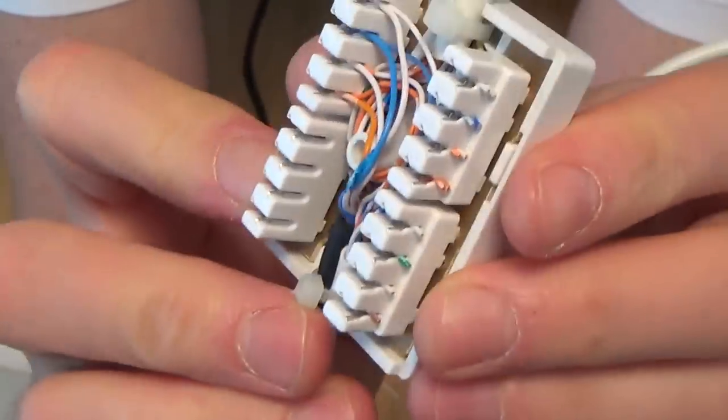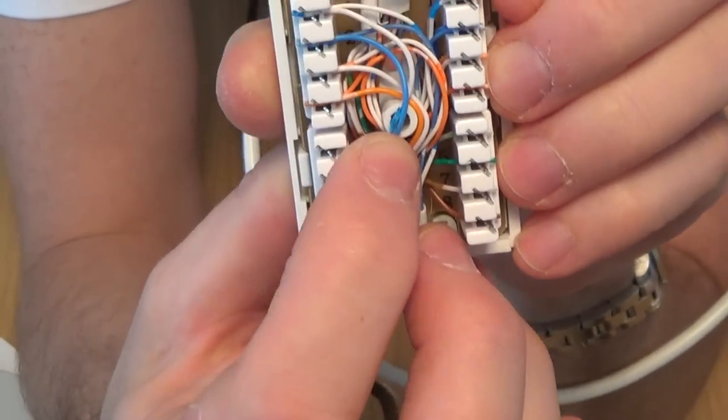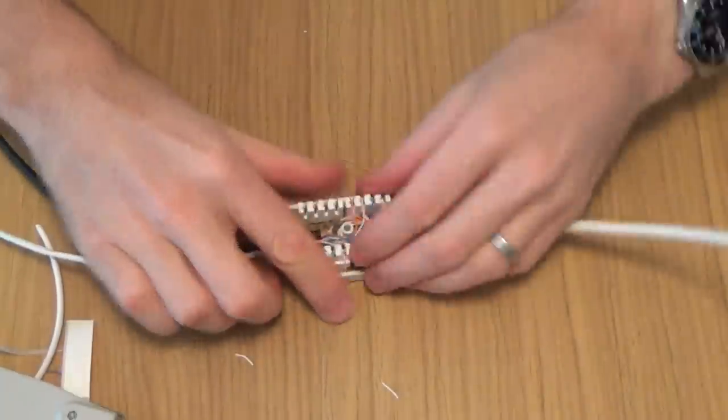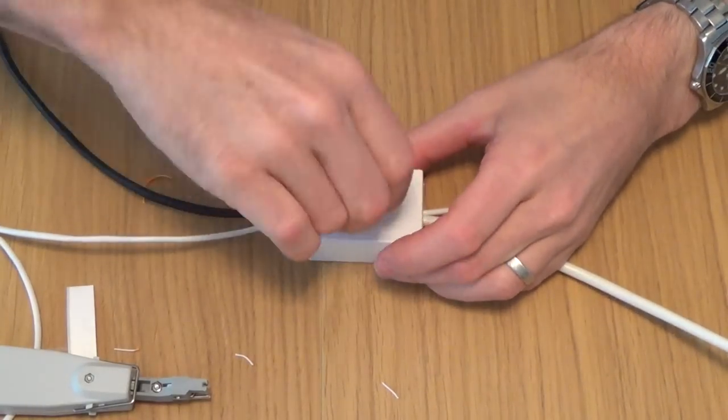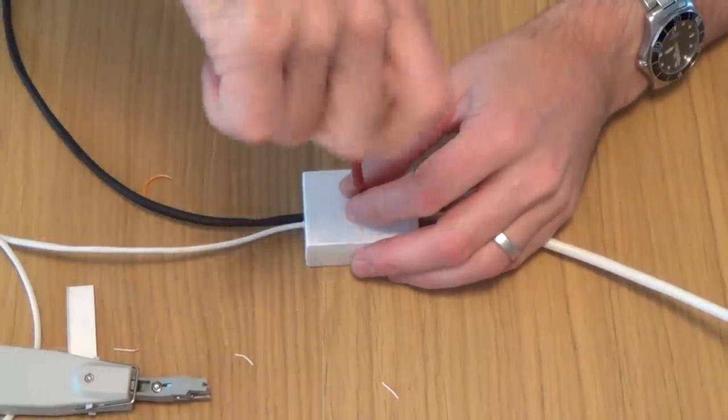You can see that when we put the lid on, that these wires are away from this hole here, because if you had the wires going over like that and you went to screw the lid on, what's going to happen is they're going to short out and then you're going to get a problem. Then you're going to be pulling your hair out trying to work out where the short is. So push the wires well away from that, and then you've just got to put your lid on. Like so. That's how you do the junction box.